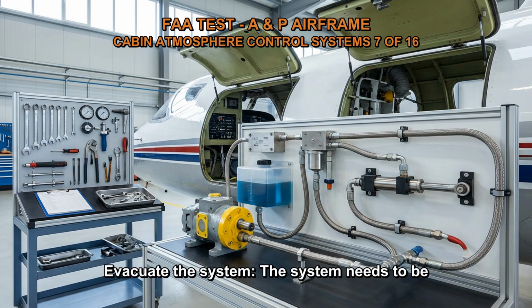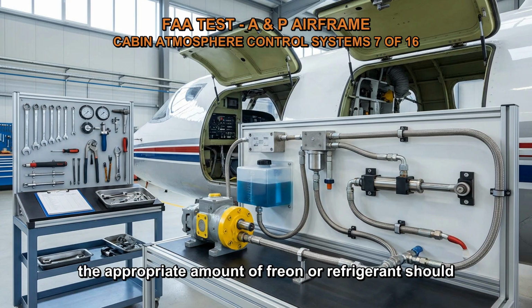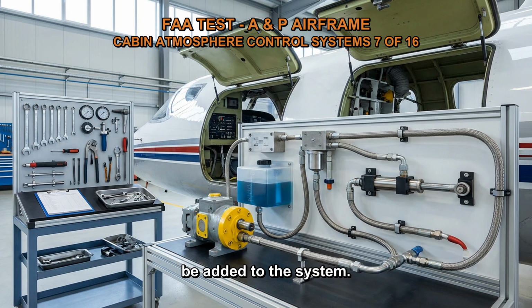2. Evacuate the system. The system needs to be evacuated to remove any air and moisture that may have entered. This is typically done using a vacuum pump to create a vacuum within the system. 3. Add Freon. Once the system is properly evacuated, the appropriate amount of Freon or refrigerant should be added to the system. This ensures that the system has the correct charge of Freon for efficient cooling.